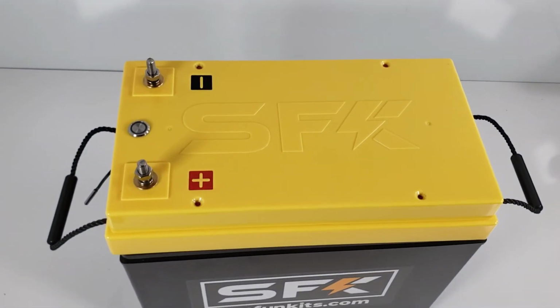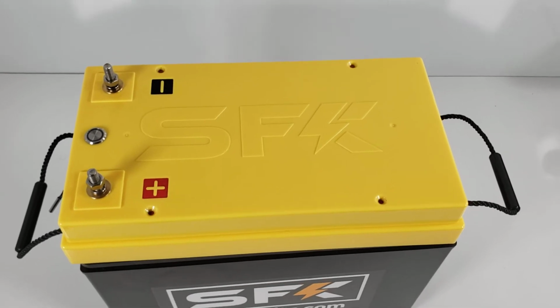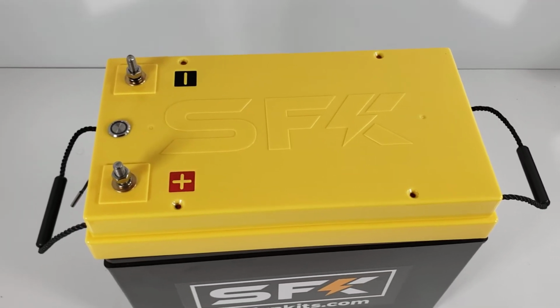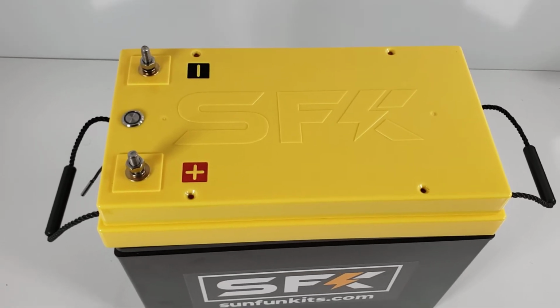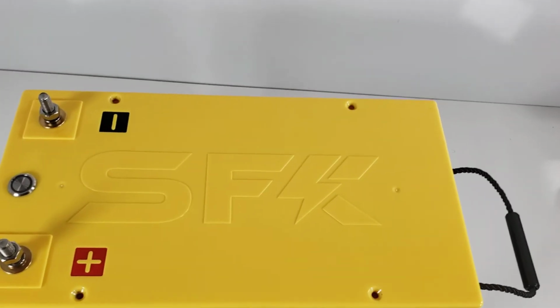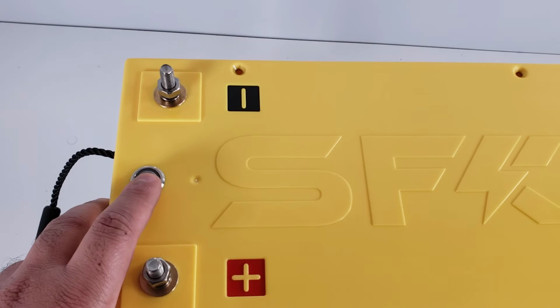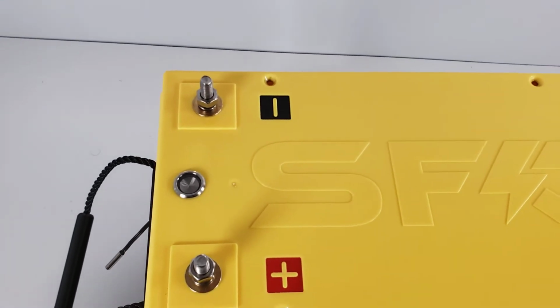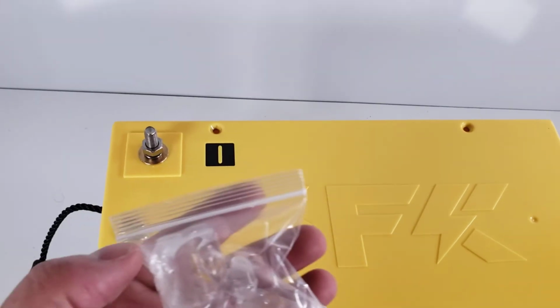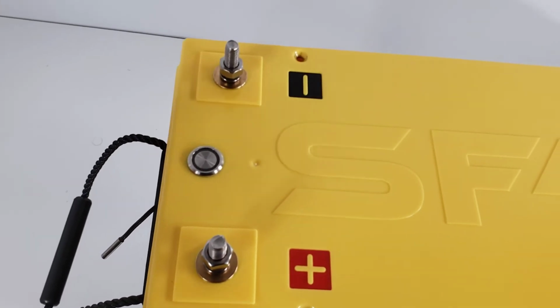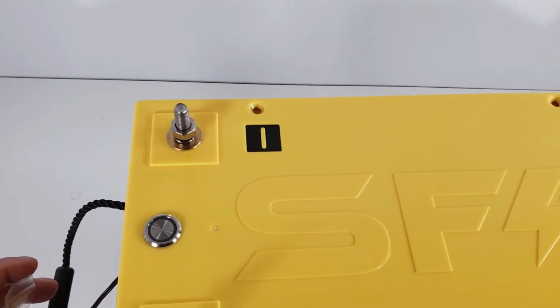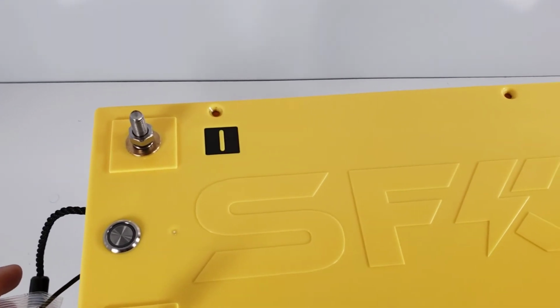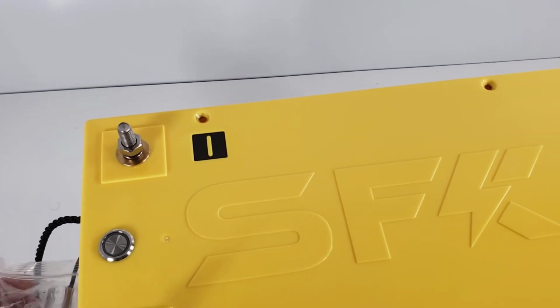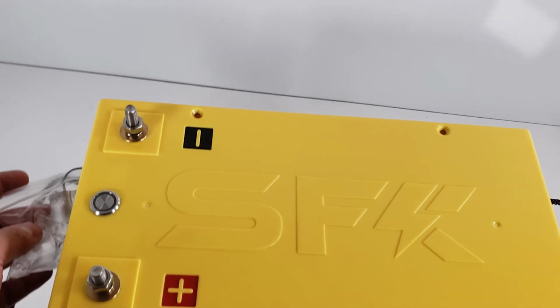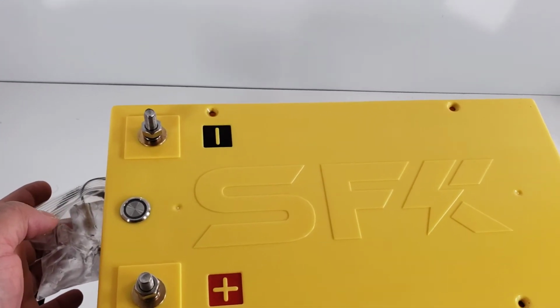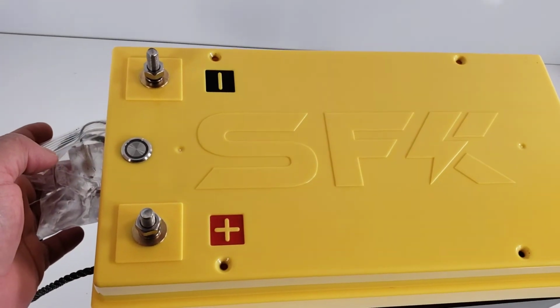The way this works is that if the temperature outside is below the threshold, for example if the thermo switch is set to 50 degrees, meaning the internal temperature of the battery gets below 50 degrees, then it will begin heating the elements, assuming you have turned on the heating system. Right now since we're indoors at 70 degrees, even if we turn it on, it's not going to do anything. So to simulate cold temperature, I have this bag of ice, and I'm going to put the thermo switch in this bag to cool it down to make the heating element available. This will only turn on if both the temperature is below threshold and the switch is turned on.